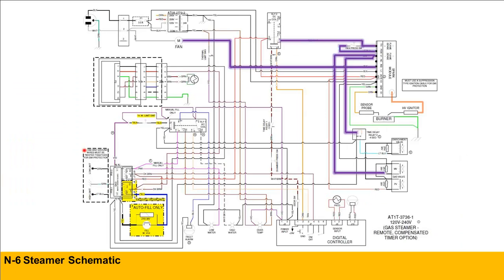All right, thank you, Dan. All right, so again, pretty much good detail as far as how the ignition circuit works, but we're going to come look at some troubleshooting. So once again, we went through the AC system. We do have our flash. We do have static pressure. I know my DC relay is pulling in at this point. So we're still not calling for heat.